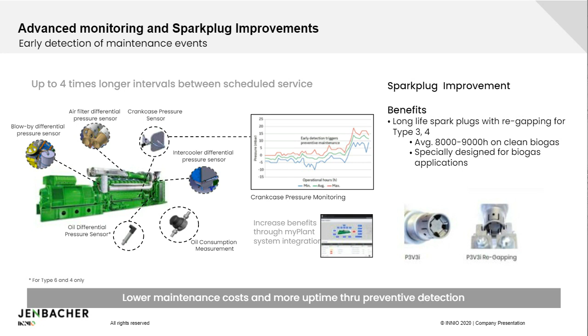The second aspect, as it relates to biogas applications, is that if your biogas is clean, our spark plugs are exceptionally long life. You could get 8,000 to 9,000 hours of life out of a spark plug, which in many cases would only last 2,000 to 3,000 hours. That's a very common number, but through these optimized spark plugs for biogas operation, we've gotten very long intervals on the Type 3 and Type 4 engines. So we're continuously trying to improve the longevity of these components optimized for biogas operations. But one of the key things to achieve low cost of maintenance and operation is really to have your gas clean. That's the one biggest thing which affects maintenance cost on a sewage plant if you're running biogas.